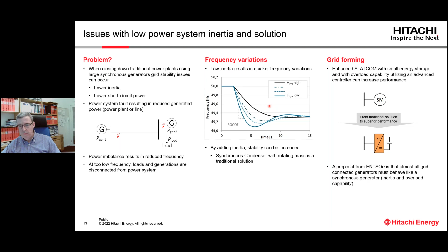And what can we do then? So if we look at the figure in the middle here, we could see the frequency of the grid that we have simulated, and we assume we start with 50 Hertz, and then at 1 second, the frequency drops down to 49 Hertz. It reaches 49 Hertz at 2 seconds, and then we keep the frequency constant. If you now look at the right figure, we start with a synchronous condenser and see the response of this frequency change. That is the blue curve we should look for here.